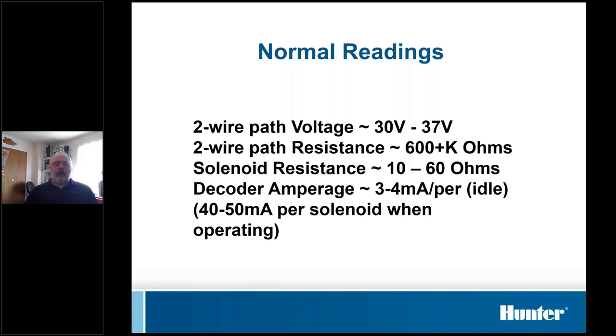As far as what the resistance should be, I always get asked. I don't use resistance much troubleshooting two-wire paths, but in an ideal world it should be higher than 600,000 ohms. There should be some resistance, but very, very high. Solenoid resistance, on the other hand, I check all the time. There's a lot of variation from manufacturer to manufacturer, so I call it 10 to 60 ohms. A 100 solenoid will read in the mid-20s, 25.8, right in that ballpark typically.